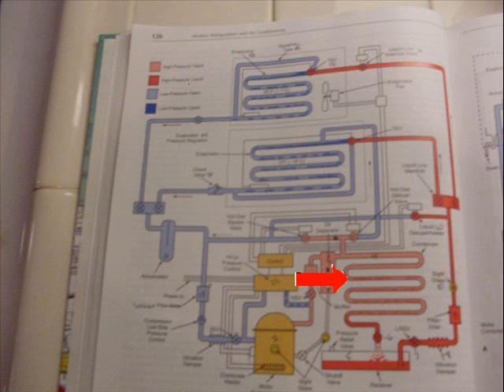Condenser removes latent and sensible heat. Takes high pressure gas, turns it into high pressure liquid. At the end of the condenser, we actually decrease the temperature of this liquid and it comes out as sub-cooled liquid.